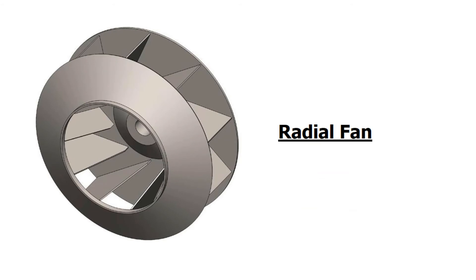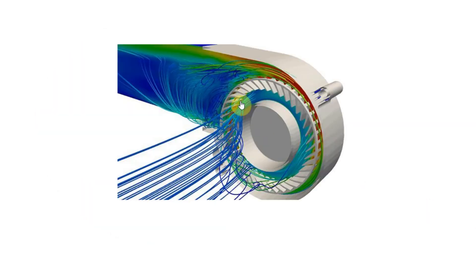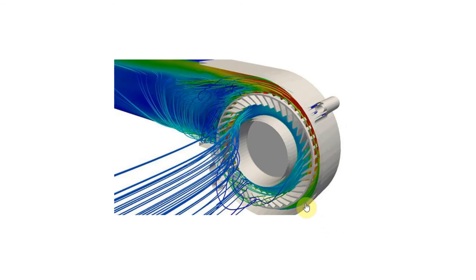The other type of fans are radial fans. The blades are arranged around the outside of the fan; the air goes in the center and comes out the side, blown out evenly around the edges. The drawing is a little out of scale — this part should expand more than shown in the diagram. You can see the air gets drawn in, then blown out around the edge. This is called a snail shell case — it's designed to expand and direct the air out. These are extremely efficient, and if they're good quality, very quiet and powerful.